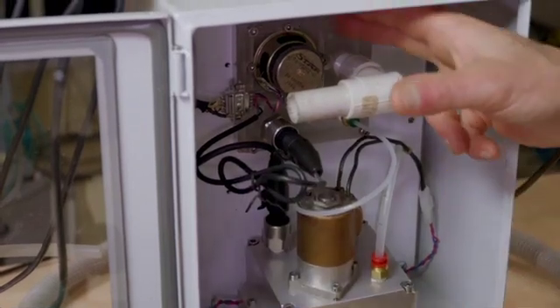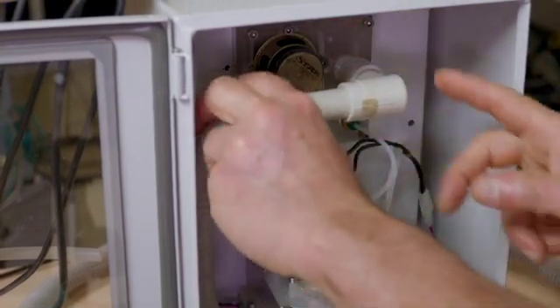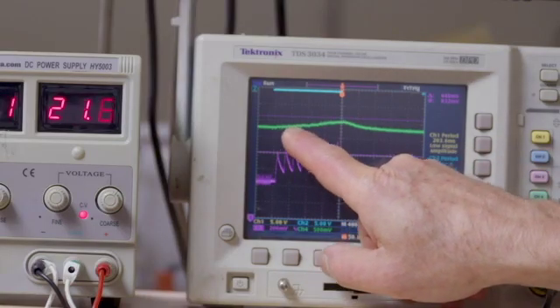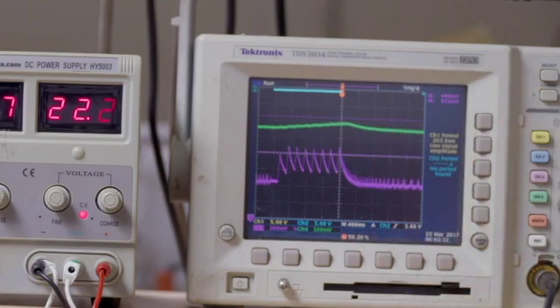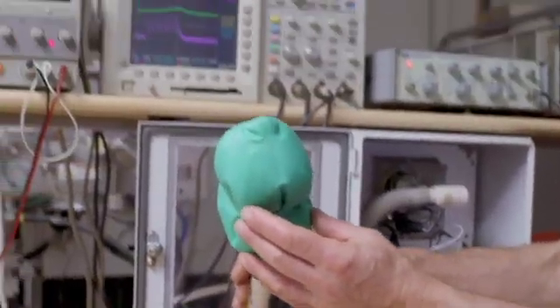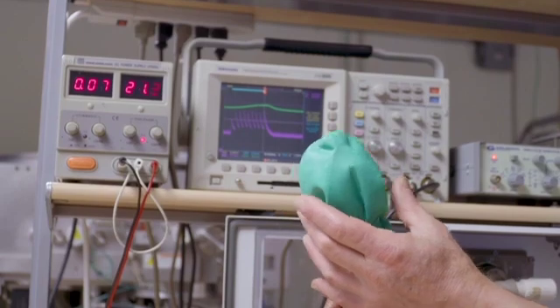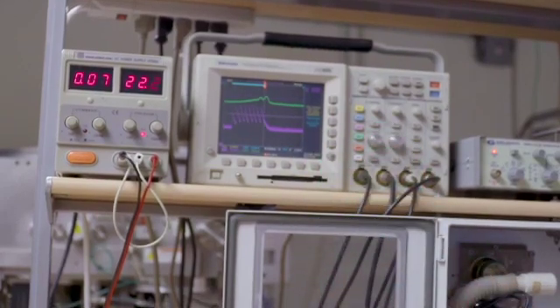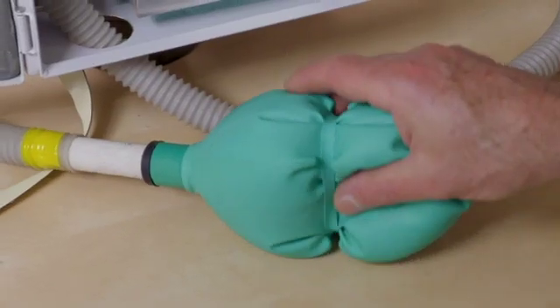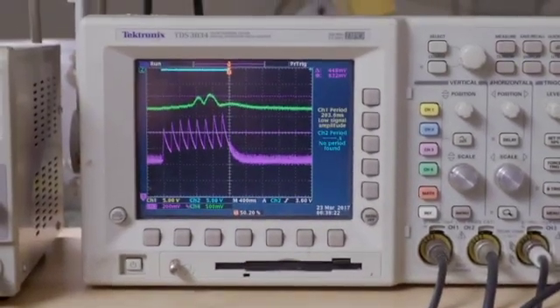We then feed this accurately controlled flow to a patient mixing chamber that has a pressure sensor attached, and we can get any desired patient flow profile by electronically adjusting our valve timing here. And this green line on our monitor screen shows the patient pressure going pretty smoothly up and down. And if our patient wants to breathe in or out, this patient pressure sensor sees that. Our electronics can then make the feed valve follow the patient's natural breathing pattern. So, no more expensive and complex parts.